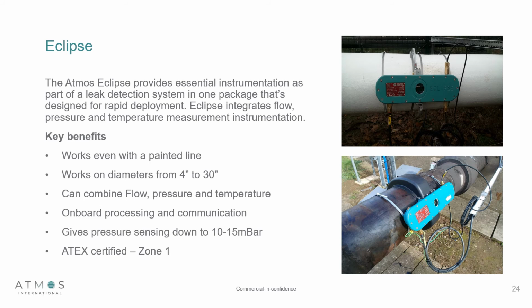The next thing that Atmos has developed is what we call the Eclipse unit. Atmos has developed this as a means of providing instrumentation into locations and onto pipelines that previously wasn't possible. The Eclipse is a completely non-intrusive hardware solution that allows Atmos to install non-intrusive pressure, flow, and temperature onto pipelines from diameters from 4-inch to 30-inch, and it will work on painted lines, not wrapped lines, but painted lines. It combines all the onboard processing and communication options that we require.